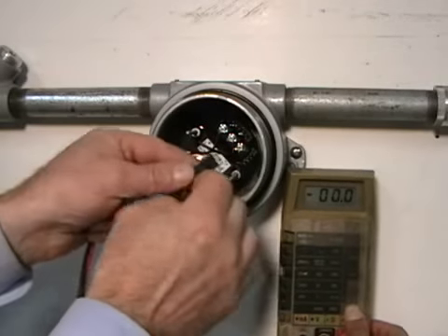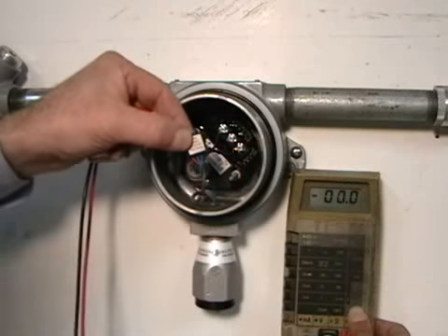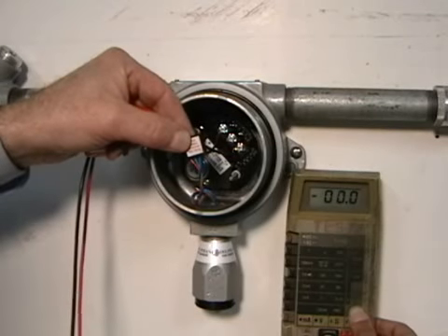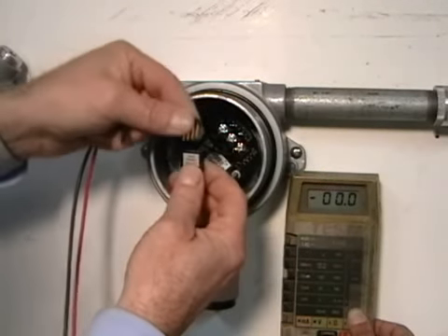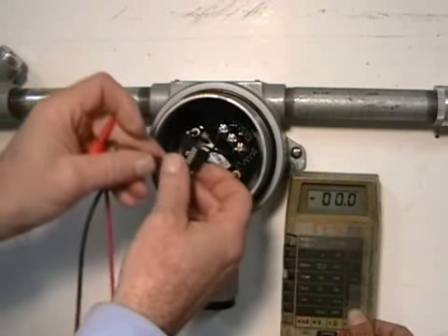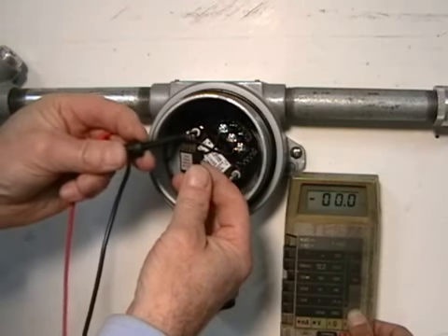The next test that can be performed is a sensor continuity test or ohm check, which will verify if the sensor elements are intact and not broken. For ease of making the connection, you can use a 4-pin header plugged into the sensor connector to give the probe clips an easy place to attach them to.